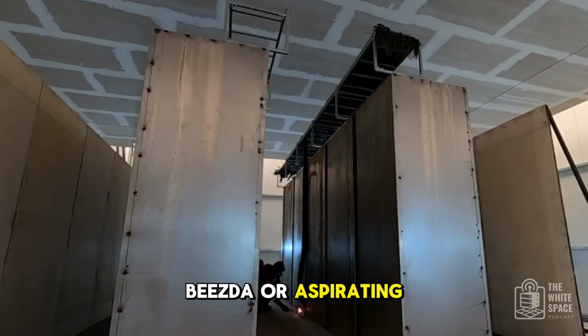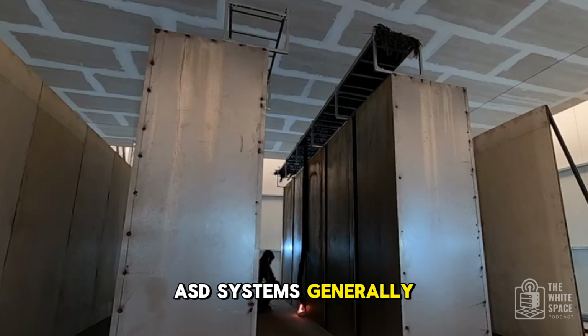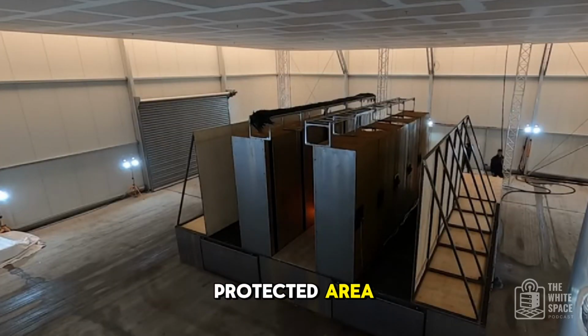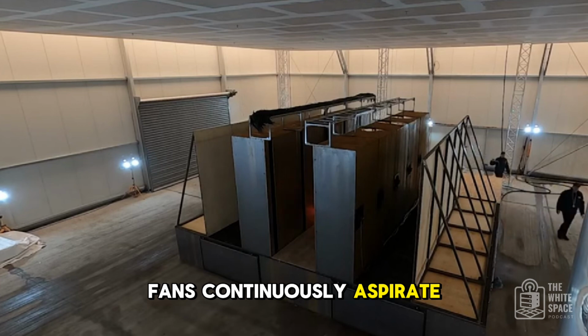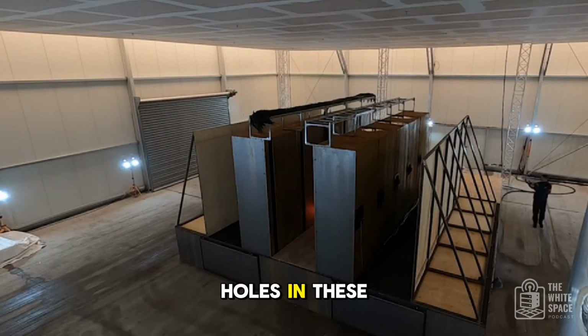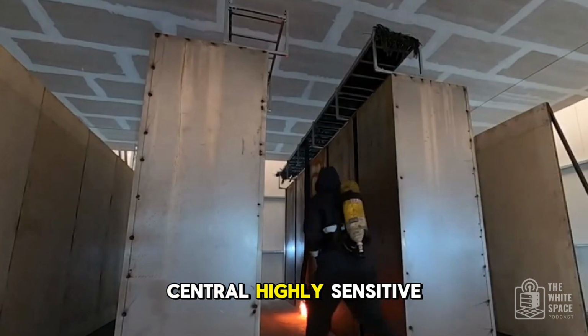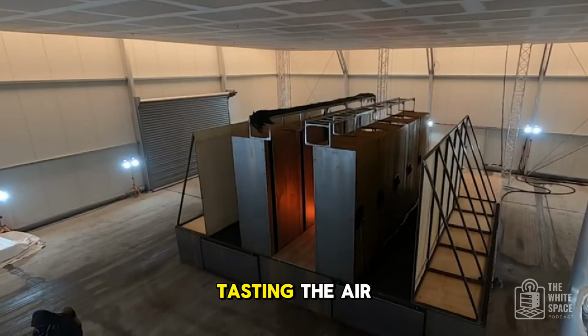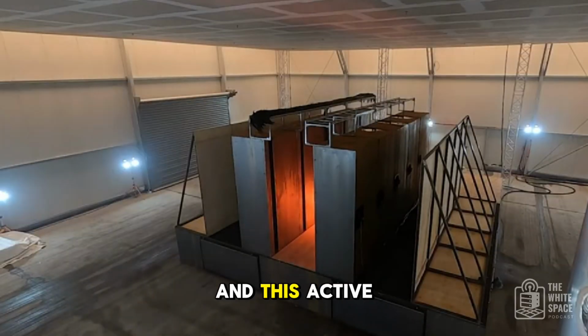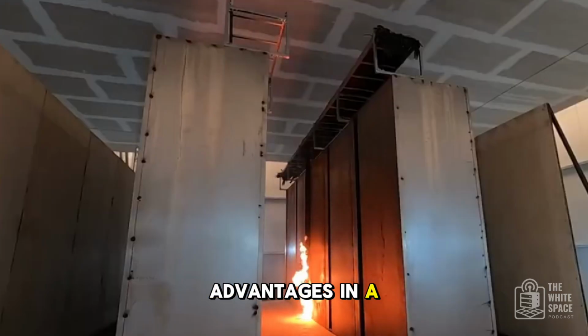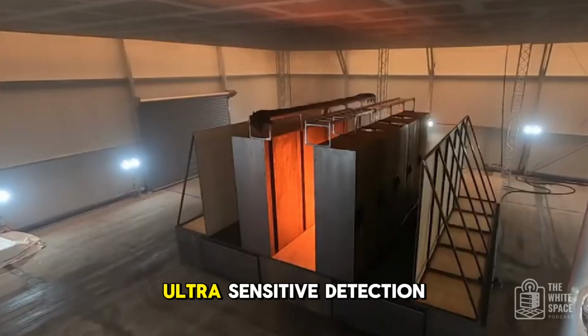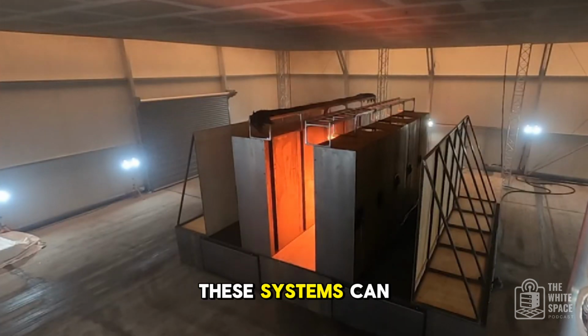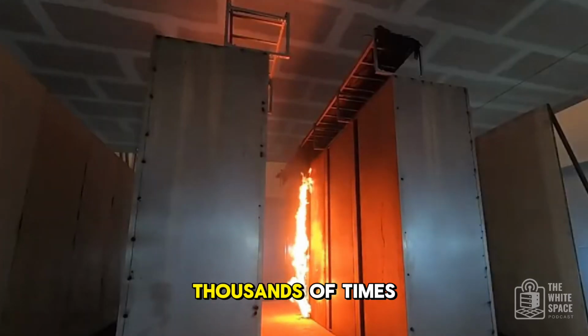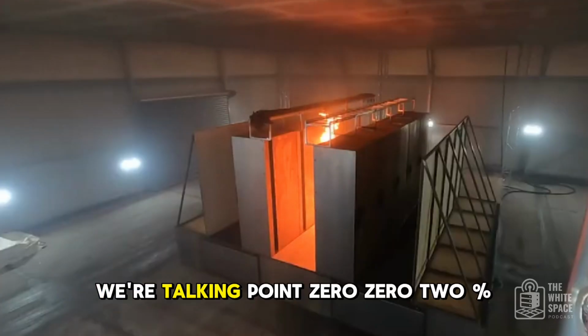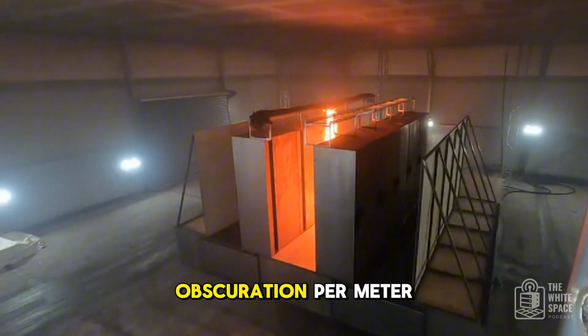Right, VESDA sucks the air in. Exactly. VESDA, or aspirating smoke detection, ASD, systems generally, use a network of pipes running through the protected area. Fans continuously aspirate, or suck, air samples through tiny holes in these pipes, bringing the air back to a central, highly sensitive detection unit. So it's constantly tasting the air from all over the room. Precisely. And this active sampling gives it huge advantages in a data center environment. First, ultra-sensitive detection. These systems can detect smoke particles at levels thousands of times lower than standard detectors. We're talking 0.002% obscuration per meter.